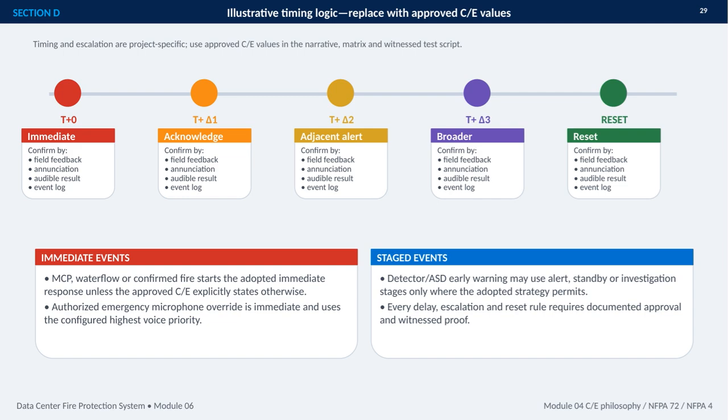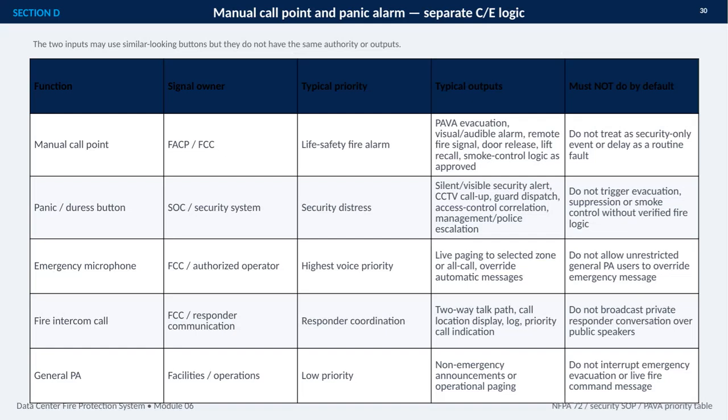Staged responses are different. Detector or ASD early warning may support alert, standby, or investigation stages, but only when the adopted strategy permits them. The final logic should align with the Module 04 cause and effect philosophy, NFPA 72, and NFPA 4.